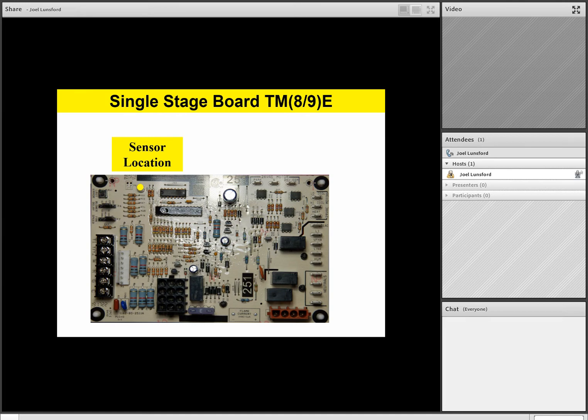Okay, let's look at another flash code. Our next flash code we're going to look at is a steady on LED. So any color LED, if it's on steady, that means that we've actually had a board failure. But we want to check some of the following. We want to recycle the power, because a lot of times, if you have an intermittent voltage surge or an intermittent power issue from the utility, the boards don't like that. And I've personally noticed that about half the time if you recycle the power, it'll go back to working. Now you're probably going to go back out there and replace the board anyway, but it's worth recycling the power to see if it'll start working again.